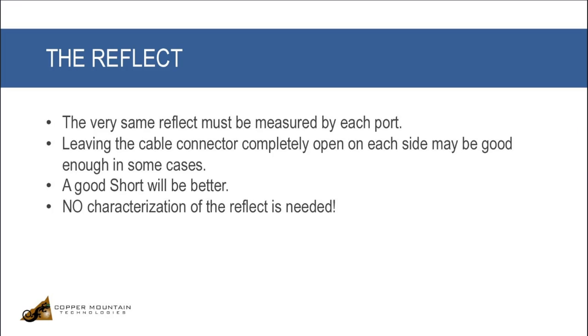That's what calibration does. So you could do, yes, you could have reflect, reflect, reflect. That is possible as long as their angles are pretty widely separated on the measurement. That's why in TRL, it's possible to use any old reflect that you like. It just has to be on the perimeter of the Smith chart.